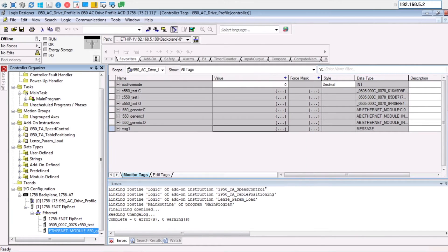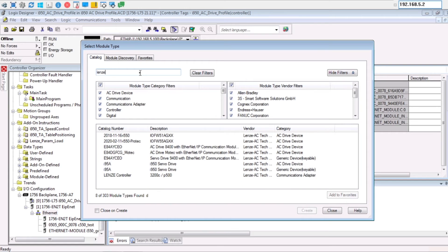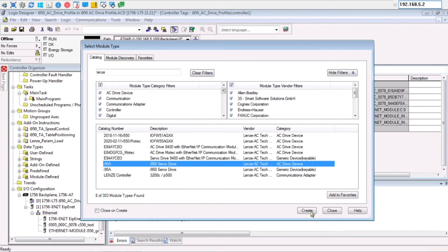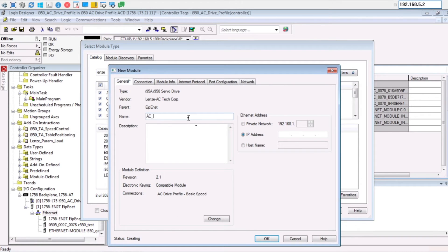Right-click on the Ethernet section of the program tree and click Add New Module. Search for Lenze devices and then click on the i950 as an AC drive device. Give it a name and some description about what you're using the device for. Then assign an IP address to it — this should be the same IP address you gave the i950 as a fixed IP address in Easy Starter.